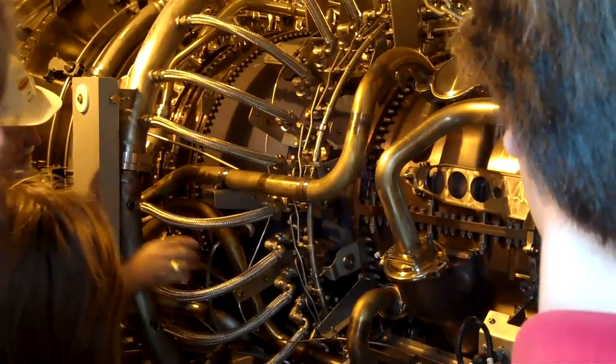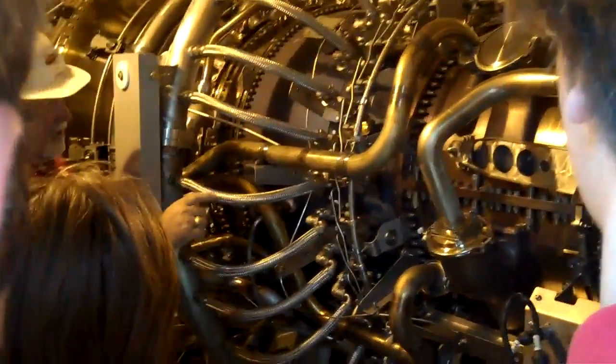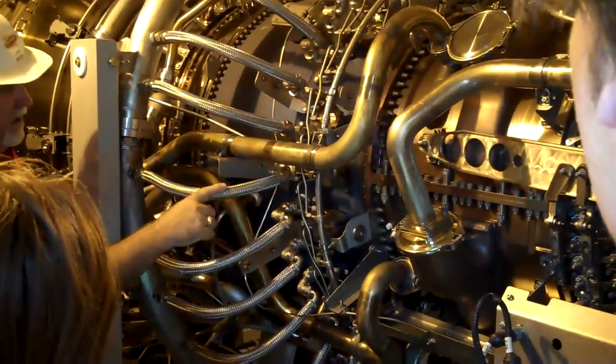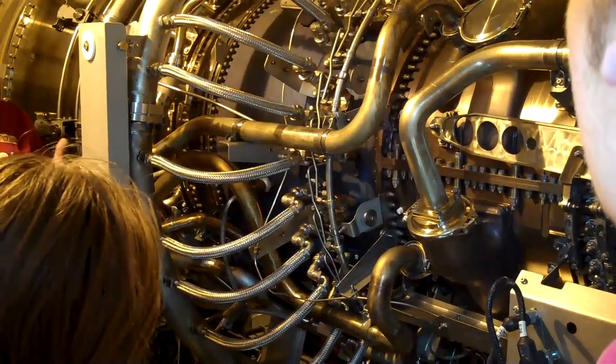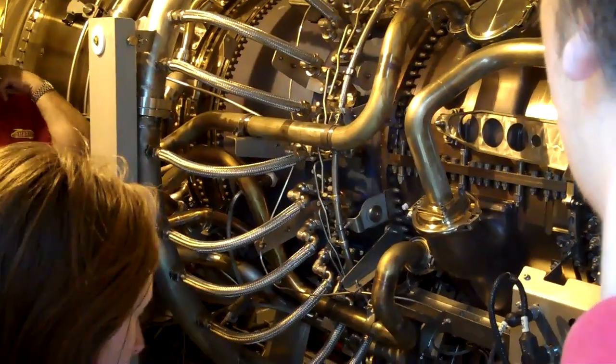So these fuel nozzles - what I didn't mention before - this is natural gas and this is actually water. So you inject water with the gas. That's one of the other ways you control the NOx, the nitrous oxides.